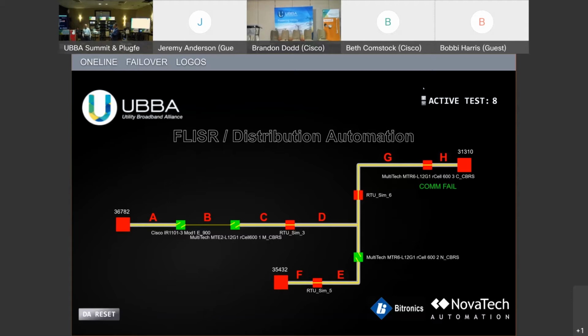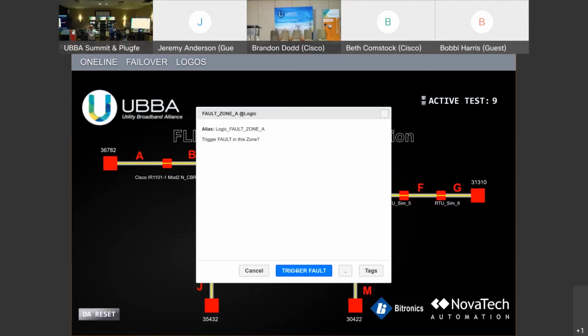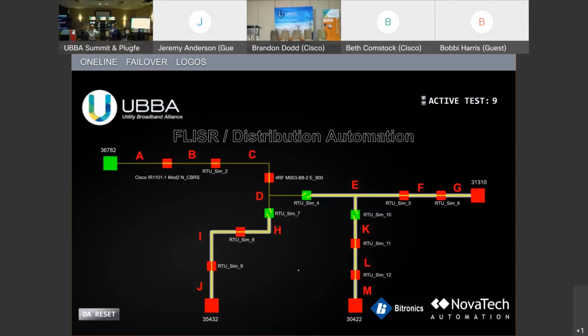Okay. All right, we're good. Any other questions in the room? Let's go ahead and continue testing. And we can go to our last test. And we're going to fault zone A. And again, we'll see that outage, lost B and C and D. We'll isolate, and then we'll close in that tiebreaker and bring back B, C, and D.